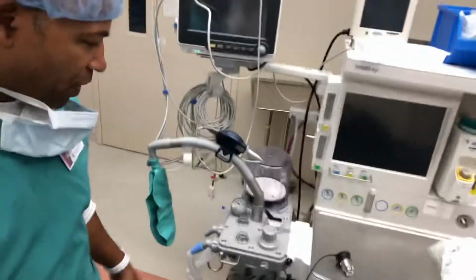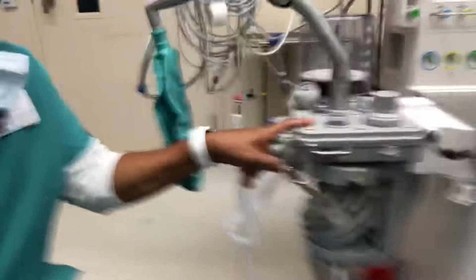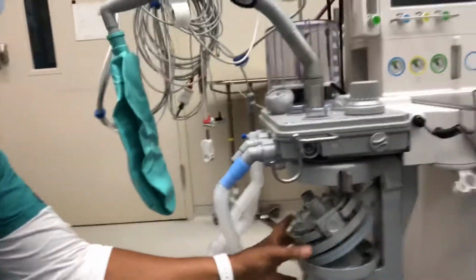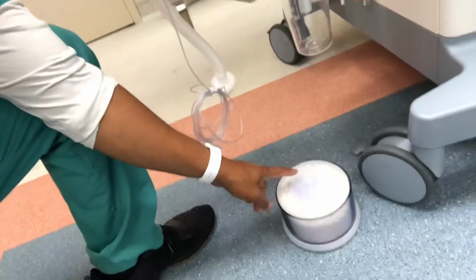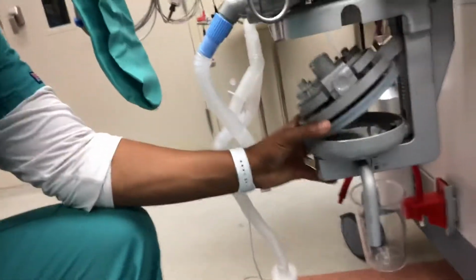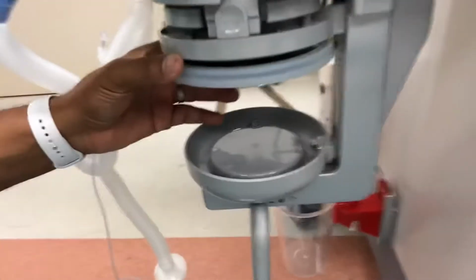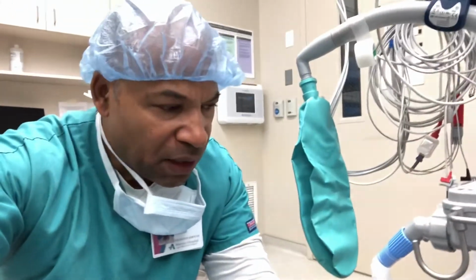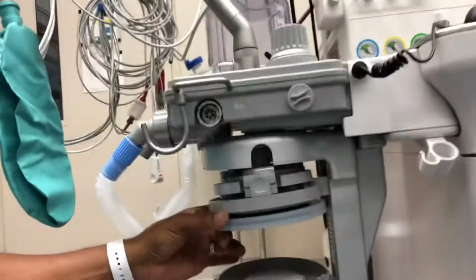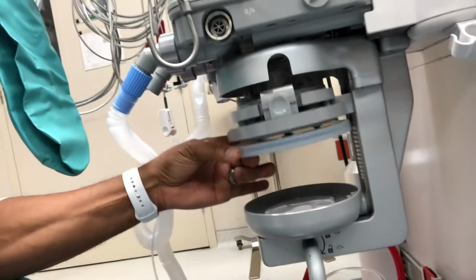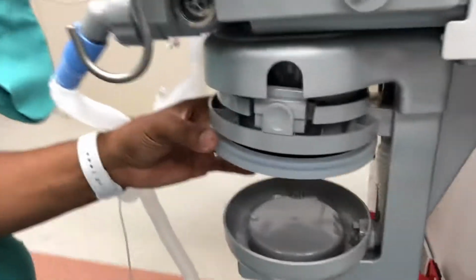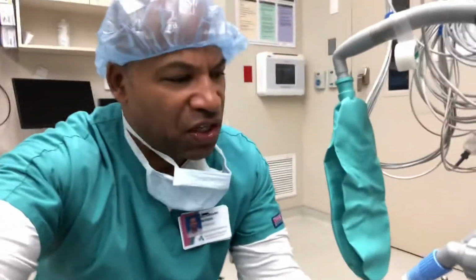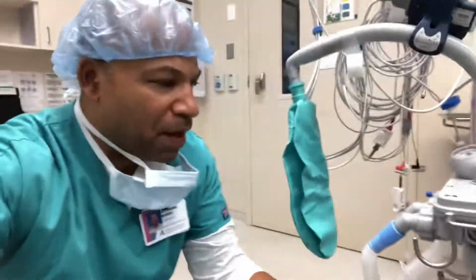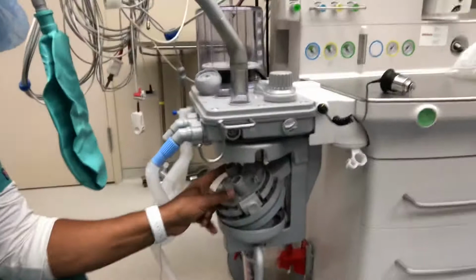On this one in particular, the A5, this is one of the areas here. This is the breathing system, and I have this one taken apart, and basically we have our soda lime here, and these are areas where we need to inspect, especially in here. I cleaned this one out pretty good, and there's a tendency for particles to fall in here, and they can actually create a leak in this area. This is an area that we want to clean often, and I want to encourage you to take some time to do that. Those of you that are maybe new to cleaning the units, follow the service procedure.